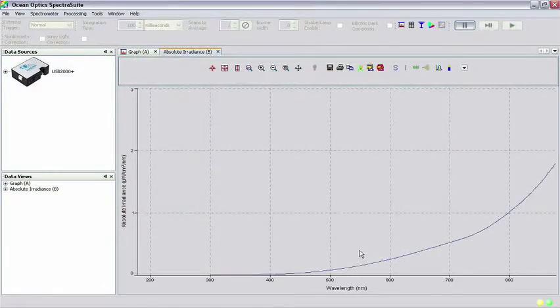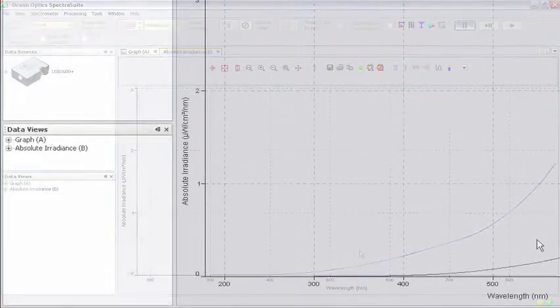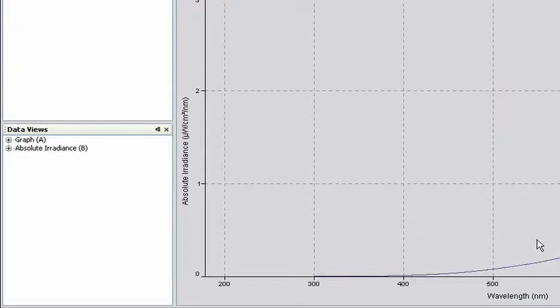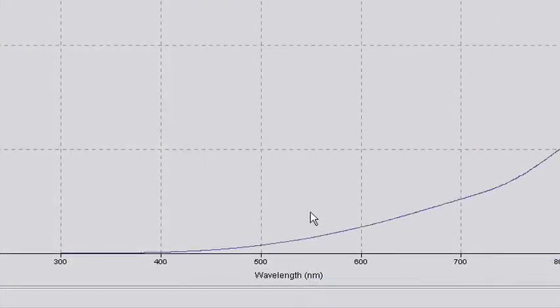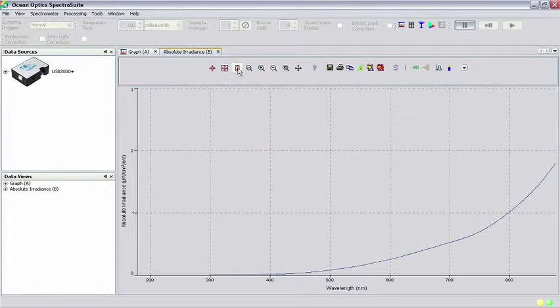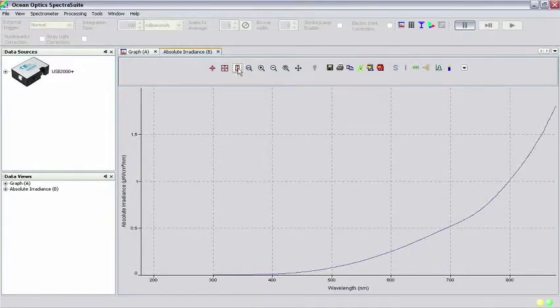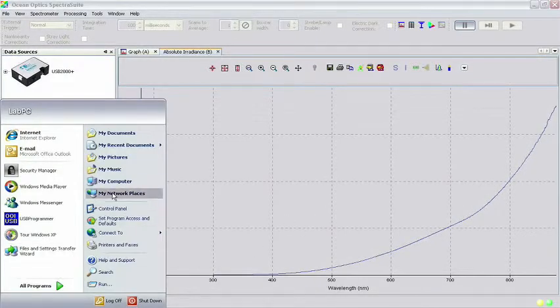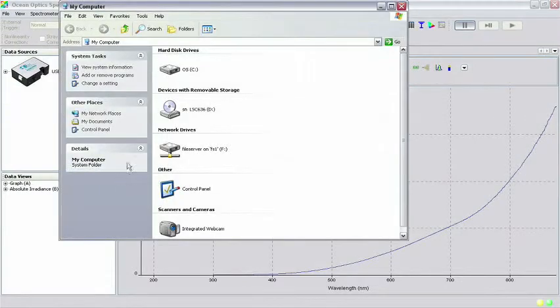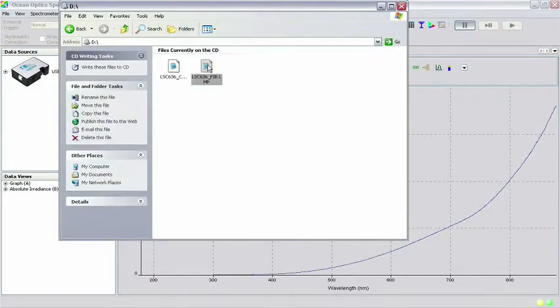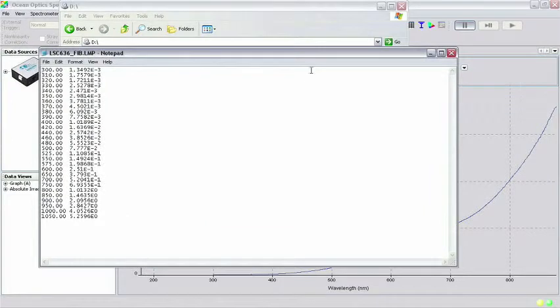In the main SpectraSuite window, you will see a graph of the calibration light source with absolute irradiance in microwatts per centimeter squared per nanometer on the y-axis. You'll also see wavelength in nanometers on the x-axis. You may have to click Scale Graph to Fill window in order to see the entire spectrum. A good check to see if you have performed the calibration correctly is to cross-reference the values listed in the lamp file with the values being measured in SpectraSuite.